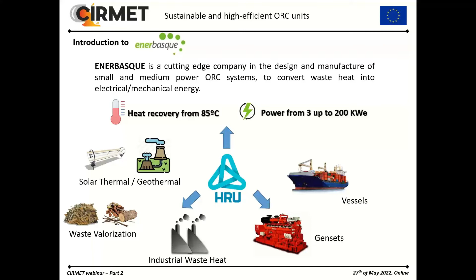Organic Rankine cycle is similar to a classical steam cycle, but the working medium is an organic refrigerant, which enables the use of low temperature thermal sources, in this case, hot pressurized water coming from the heat exchanger that captures waste heat from flue gases. This water enters into the ORC at 115 degrees Celsius. Here is shown a scheme of our ORC system.